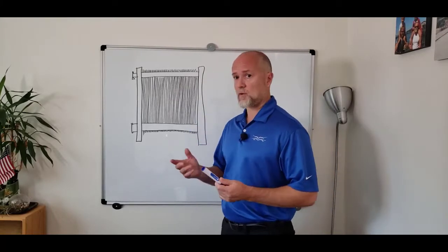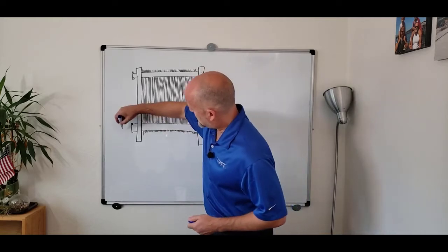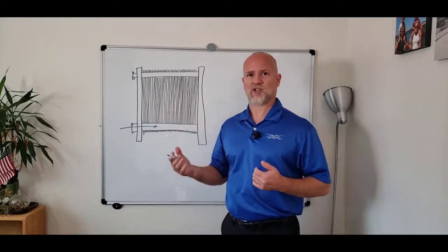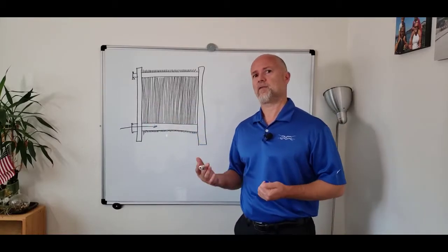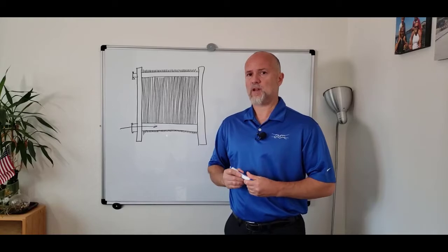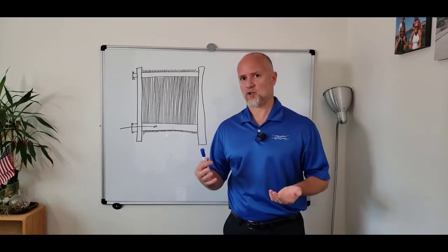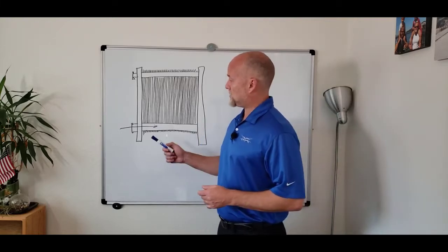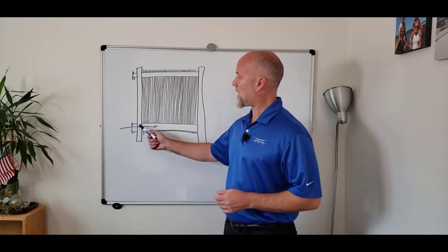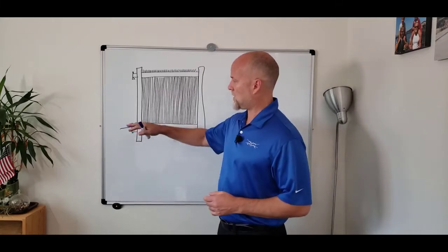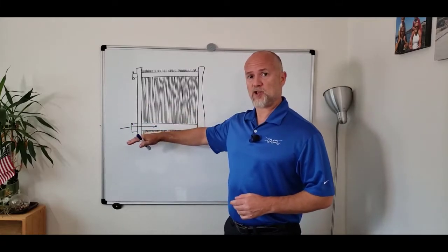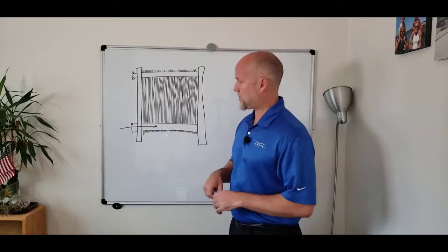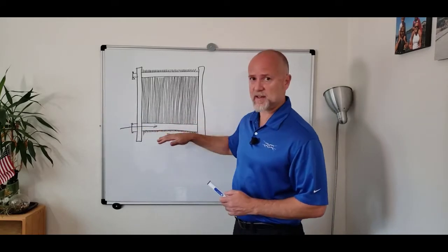Well, first of all, if you imagine, this is the inlet, let's say the cold inlet, which normally is the more challenging because it comes from the cooling tower, so you might have debris, you can have fouling issues. So the cold inlet normally is the most challenging one. And that's the reason why we suggest to always put it at the bottom of the heat exchanger and not at the top, so you can take advantage of the positive pressure coming from the pump. So you imagine that this is the inlet.